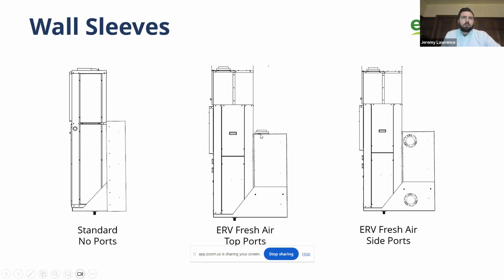In this case, both ports are on the top of the unit, and the fresh air is piped down through the sleeve into the fresh air space below the condenser. And then so on that is one. Yep. So is there a concern about the cold air or the fresh air entering the living space through the sleeve then? So no, because anytime the condenser fan motor is, so the way to consider these units is so that with this being the condenser right here, anytime it's running, it's pulling air in and pushing it out. But even when it's not, inside this unit is technically exterior to the building. So the unit itself is insulated, and so there's only very few instances where we ever have condensation building up or frost.